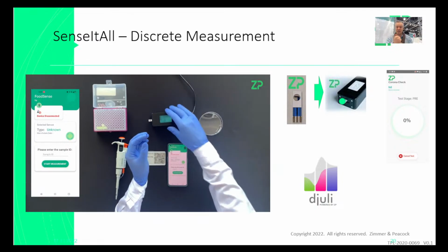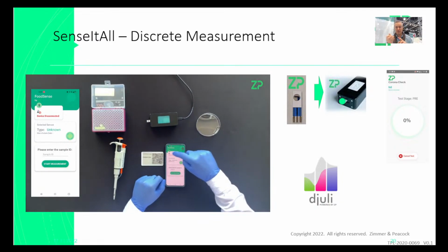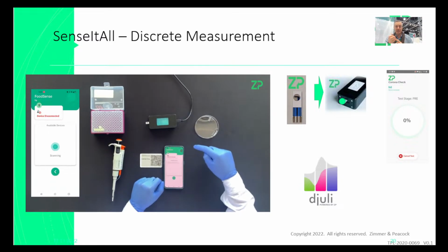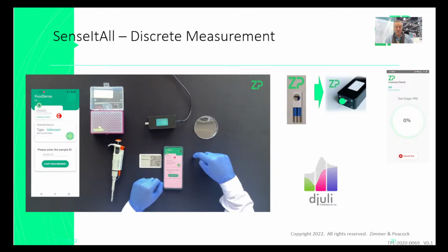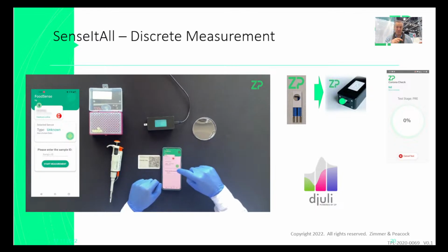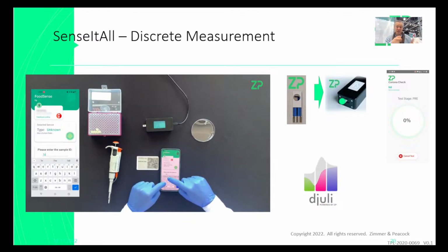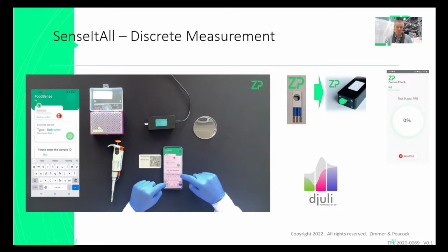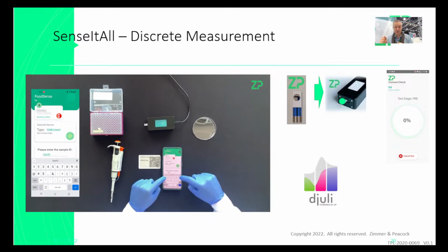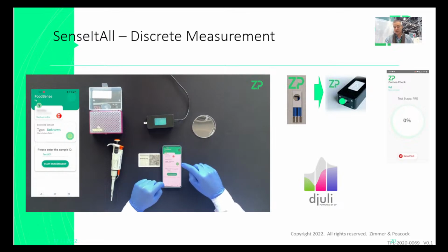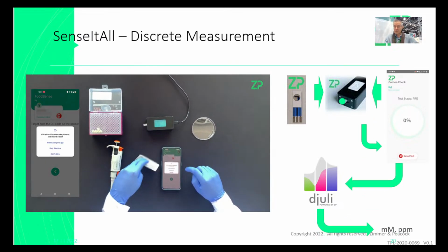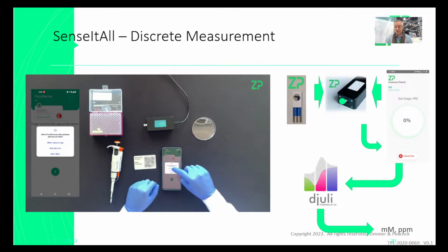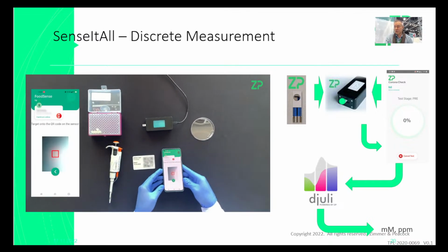Sensor can stay consistent, electronics can stay consistent, djuli stays consistent. It's just the app, when it's doing the excitation, the app is telling the meter what to do. When the meter does that excitation, it's a different protocol depending on what we're trying to analyze. And then the data goes to djuli, and it's a different protocol for what we actually want to extract. And so we send the data to the cloud, and the cloud extracts information.